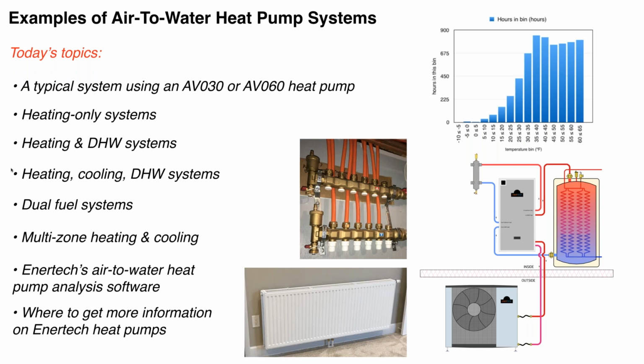That's where we bring another boiler, another heat source, typically a boiler, into the system, and it can serve as a backup. It could also provide heat when you have on-peak electric rates. Some of you may have what are called time of use electric rates, where during the off-peak period, it would be beneficial to provide the heat through the heat pump, lowering the cost of the energy. And during on-peak periods, the boiler could provide that heat. So there is a model of the Advantage unit that is set up with controls to automatically operate that boiler when necessary. And then we're gonna branch out into multi-zone systems, where we have several zones in heating and potentially even several zones in cooling.